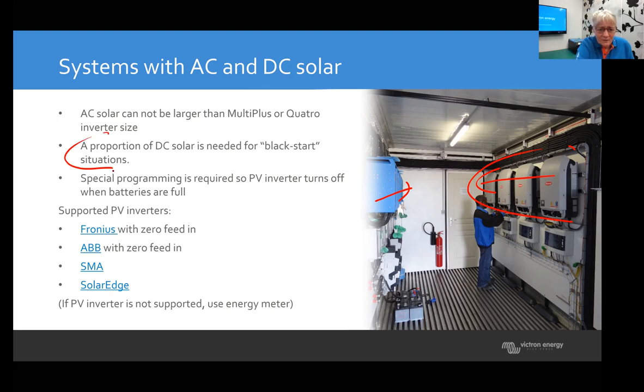We always recommend to have a proportion of DC solar in a system like this. The DC solar is needed for black start situations. A black start situation means that early in the morning, let's say at night, there's no sun coming in, of course, grid feed inverters are off, and then for whatever reason, you've let the battery go down too much. So it's the end of the night, batteries are flat, the inverter has stopped, and the inverter creates the grid for the AC inverters. The sun comes up in the morning, the PV inverter wants to work, but sees no grid and is not allowed to turn on.